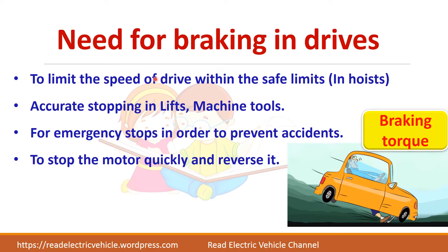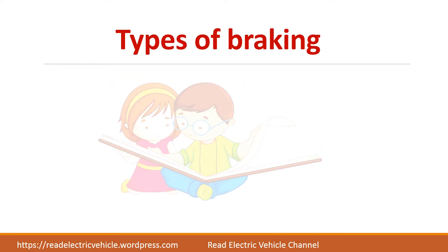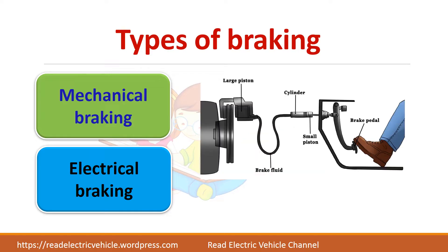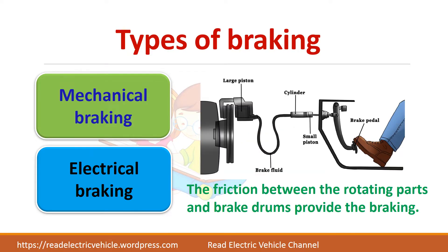For all these cases, you have to somehow develop the braking torque either electrically or mechanically. There are two types of braking: mechanical braking and electrical braking. In mechanical braking, the friction between the rotating parts and the brake drum provides the braking. There are some drawbacks with mechanical braking, so normally electrical braking is preferred in electrical drives. In most applications, both electrical braking and mechanical braking systems will be provided, because electrical braking alone may not be sufficient at all conditions.